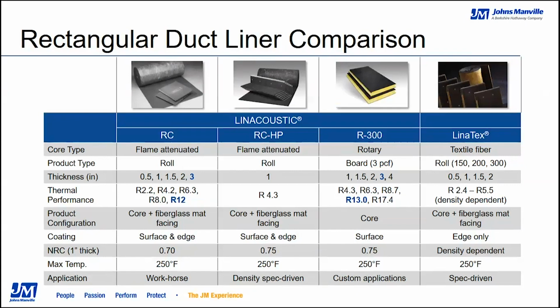That's really important to make sure you're getting a consistent thermal R value across the duct liner as you're installing that product. Our LINACOUSTIC RC product has an edge coating on both of the outside sides that you can see on that roll, and it also has a coating over the airstream surface side. So the side of the duct liner exposed to the airstream has our proprietary Permacote coating, which is a great feature of that product. It does a nice job for water repellency and inhibiting microbial growth, and it's a very durable product, a little bit stiffer and tougher than a traditional fiberglass mat.